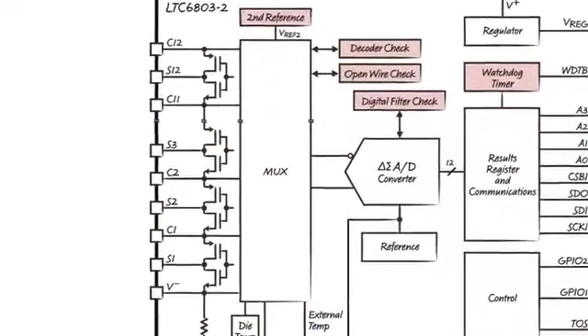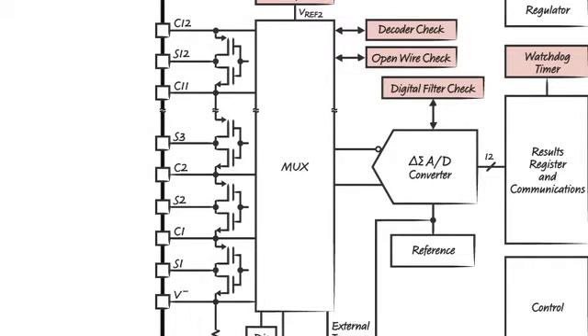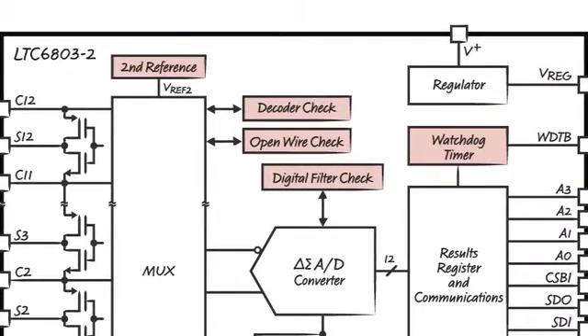A multiplexer connects the battery cells to the ADC. A stuck address line in the IC could cause some measurements to be skipped. The decoder check block guarantees that every cell is measured every measurement cycle.